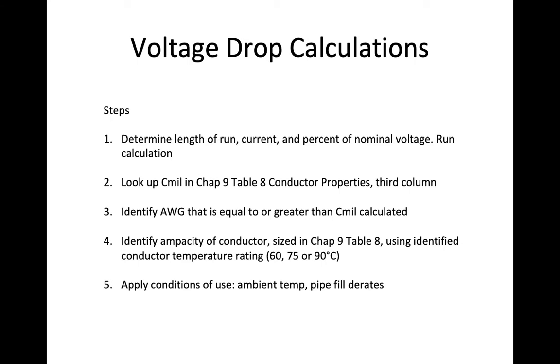So I'm going to go from Chapter 9, Table 8, to my table 310-15B-16, and identify a conductor that can handle, or identify the ampacity of that particular conductor. And then after that, Step 5, you apply any ambient temperature derates or pipe-filled derates.